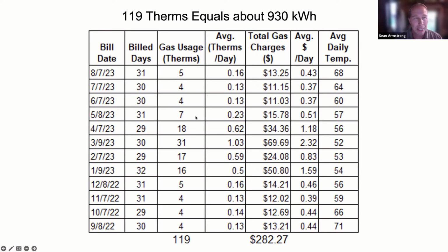Now I'm going to take that number and say all these gas devices, at best, are only getting 80% of the energy into what they're doing. The gas furnace, the gas water heater, they're at best 80% efficient. So I'm going to multiply 119 times 29.3 times 0.8 - that's an important step, to say only 80% of it's being used. Now the final step is to divide that number by 3, which represents the efficiency of the heat pump, where 1 unit of electricity goes in and 3 units come out.